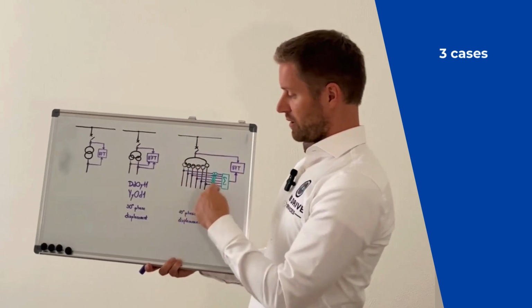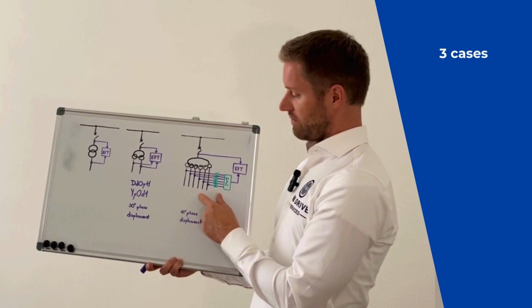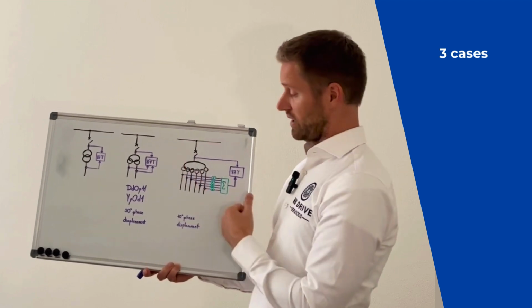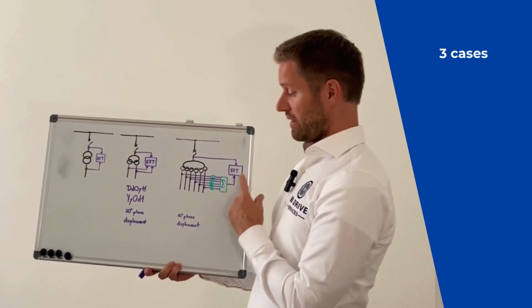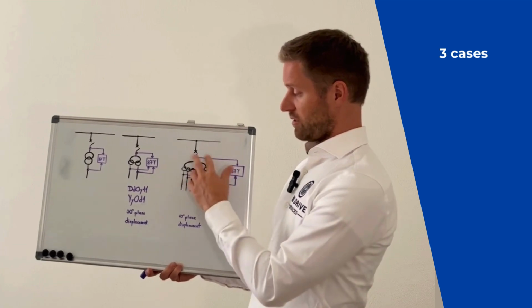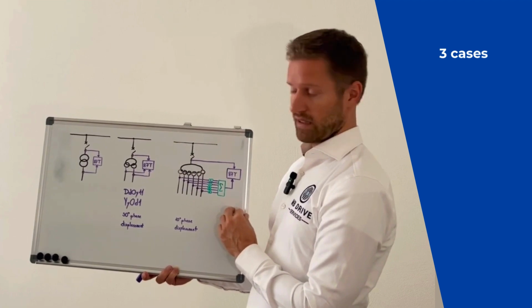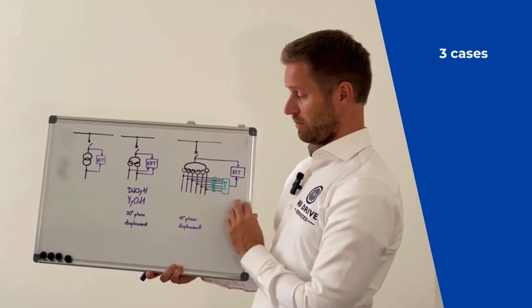However, if you have a more complex transformer, like this one, or even more secondary windings, then the relay would not support such a configuration of the transformer inherently. So we need to find some workaround.